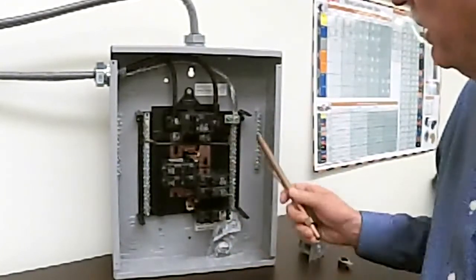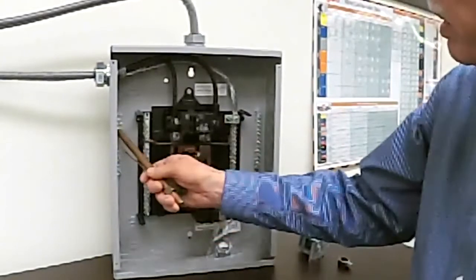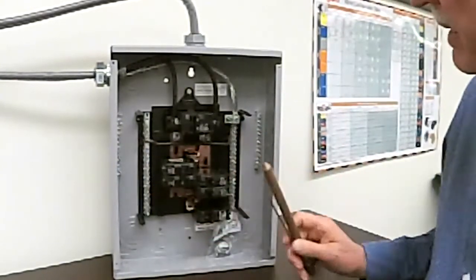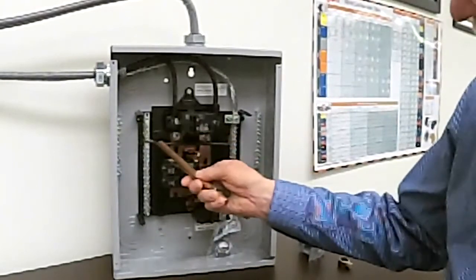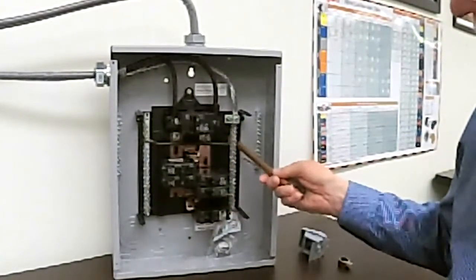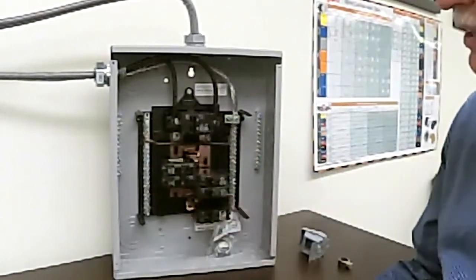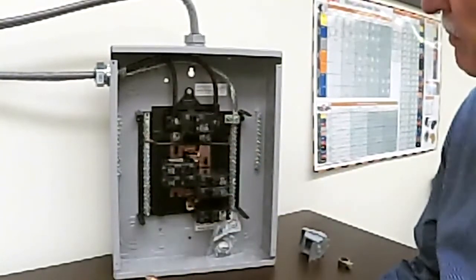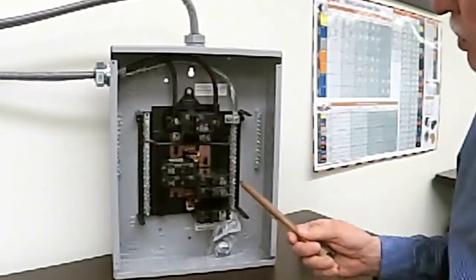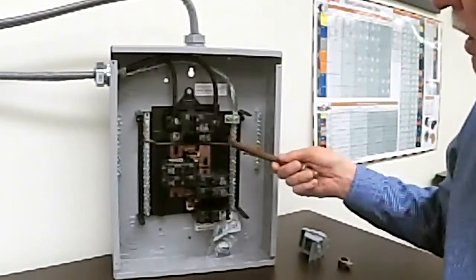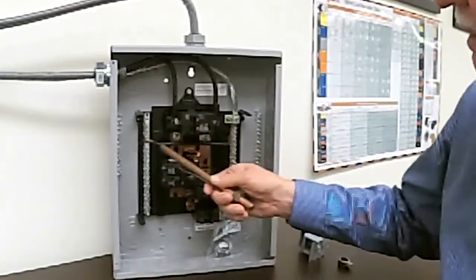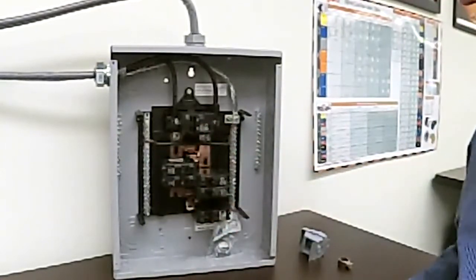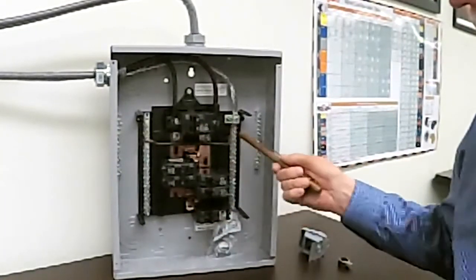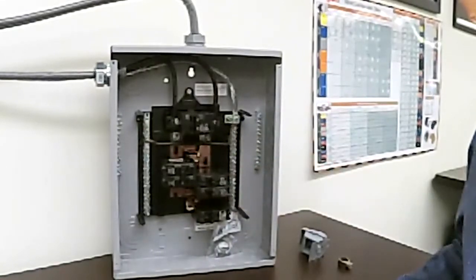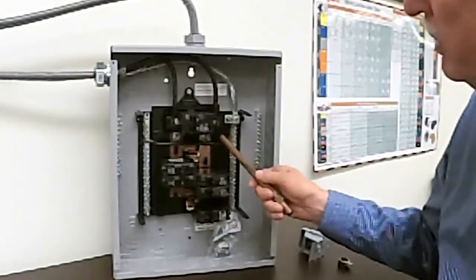The next thing we have here is the neutral bars, 2 neutral bars and 2 ground bars here. This copper bar that jumps across from neutral bar to neutral bar is not meant to be removed. I had a contractor, I went to do an inspection one time, and this bar here was cut out. He cut it at both ends. He says, Rich, I hope you don't mind if I had to cut the bar and leave it there. I couldn't undo the screw. Well, don't you think there's a reason you couldn't undo the screw? This bar is not made to be removed.